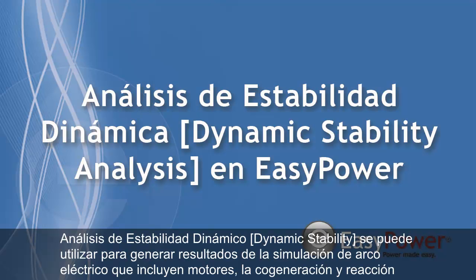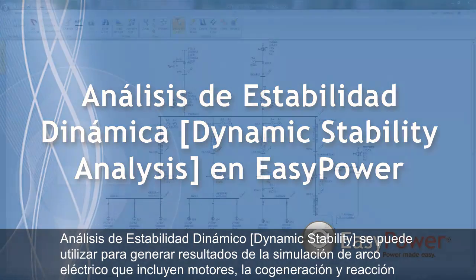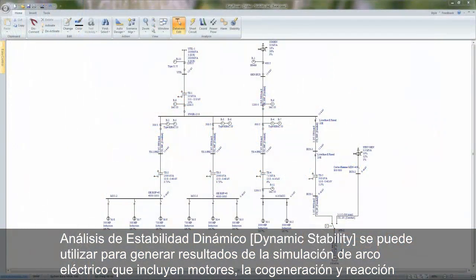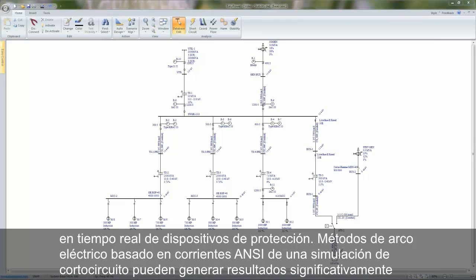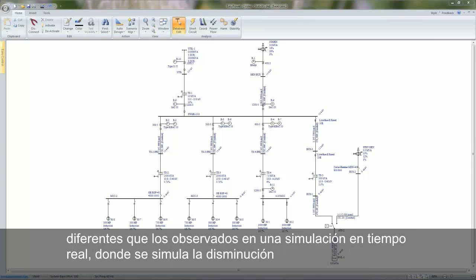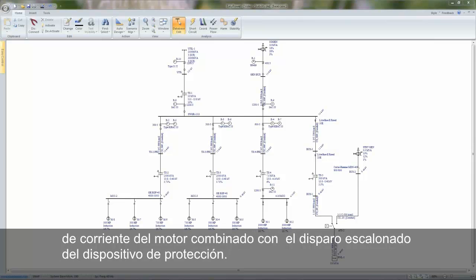Dynamic stability analysis can be used to generate arc flash simulation results that include motor, cogeneration, and protective device real-time response. Arc flash methods, based on ANSI currents from a short circuit simulation, can generate significantly different results than seen in a real-time simulation where motor current decay and protective device staggered tripping is simulated.